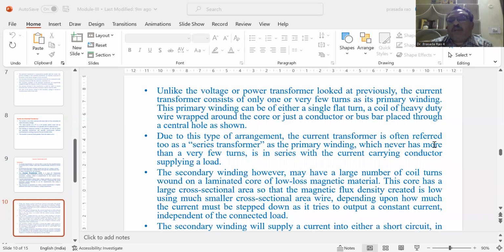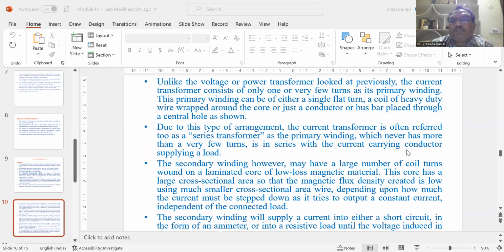Due to this type of arrangement, the current transformer is often referred to as a series transformer, as the primary winding, which never has more than a very few turns, is in series with the current carrying conductor supplying the load. The secondary winding, however, has a large number of turns, wound on a laminated core of low magnetic loss material. This core has a large cross-sectional area so that the magnetic flux density created is low, using much smaller cross-sectional area wire, depending upon how much the current must be stepped down, as it tries to output a constant current independent of the connected load.